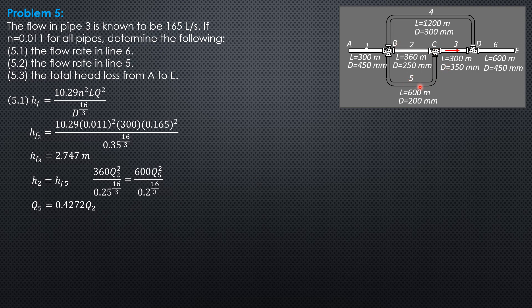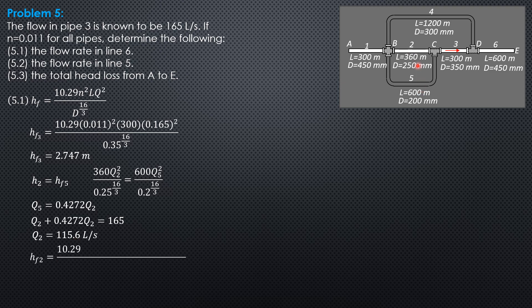Then Q2 plus Q5 equals 165. Substituting: Q2 plus 0.4272 Q2 equals 165. Solving gives Q2 equal to 115.6 liters per second. Having known Q2, we compute HF2: 10.29 times 0.011² times 360 times 0.1156² over 0.25 to the 16/3. So HF2 is equal to 9.737 meters.